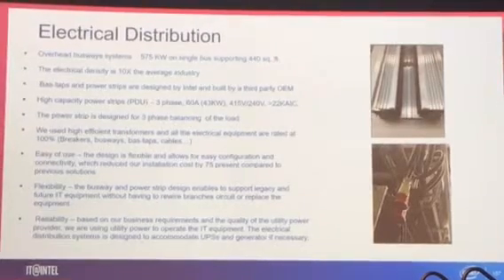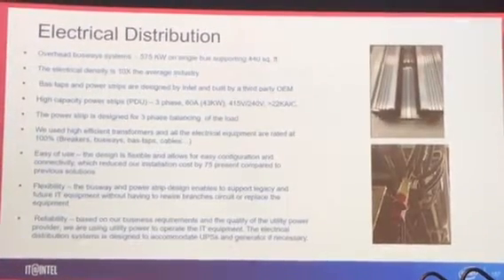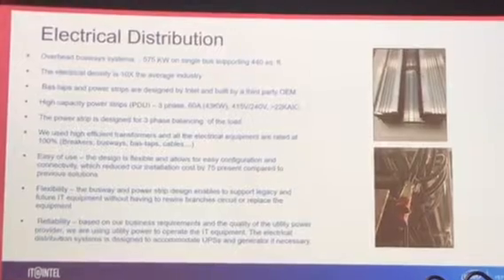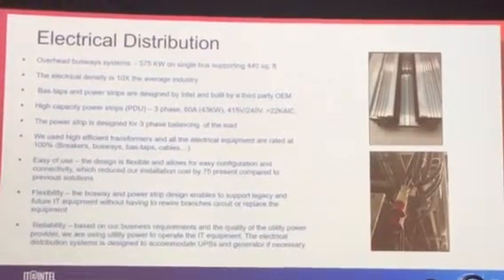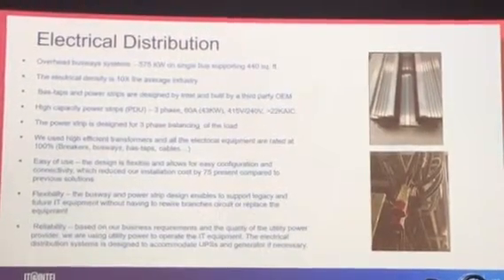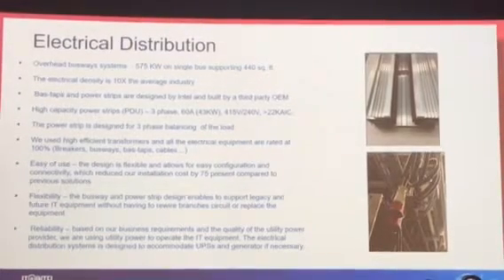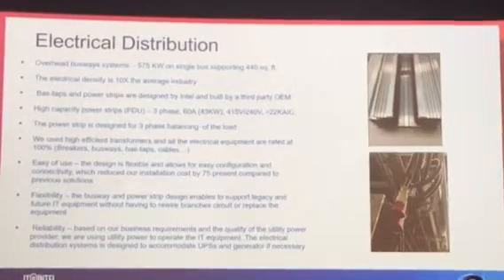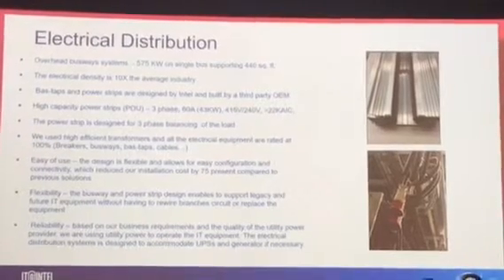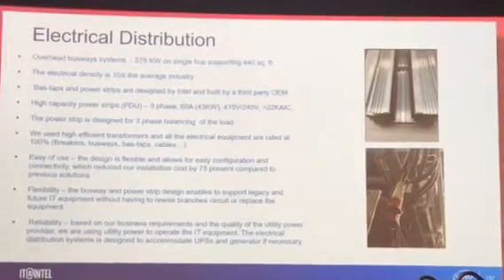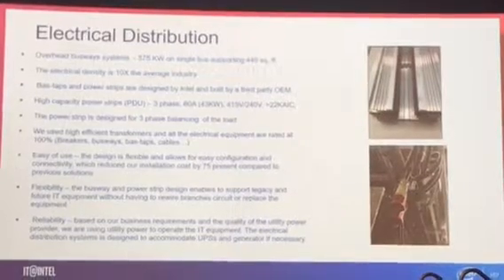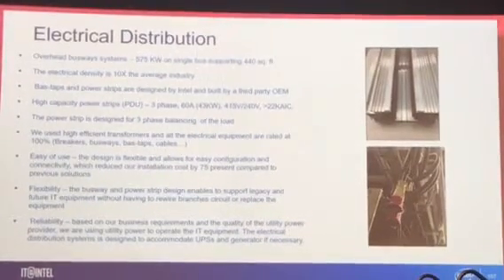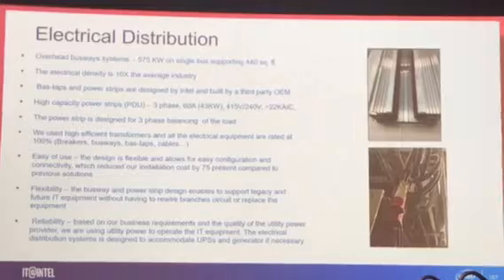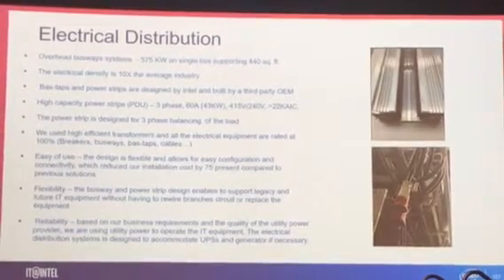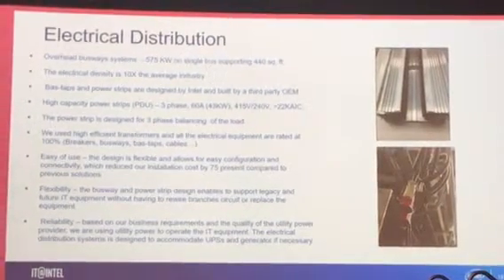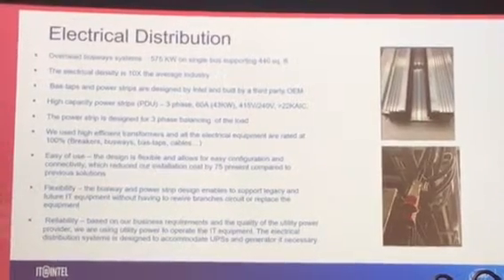The transformer, like I said, 100%. The design is flexible. You know, busways, it's easy to maintain. If you need to replace the bus-taps, just remove them, replace to a different type, size, no issues. There's a lot of flexibility with this data center, and then reliability is high. Again, we don't have a lot of equipment. We don't have CRAC units. We don't have chimneys, no raised metal floor, flooded air over there.